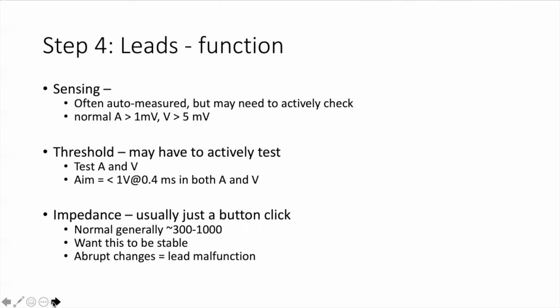Pacing threshold. Sometimes devices have an auto threshold check, though it's ideal to check the threshold yourself if the clinical question is whether the device has a lead malfunction. If they're looking to see why the patient was shocked for VT, it may be less necessary. To actively test, you're going to have to go to the tests tab on the device, and essentially you increase the rate on the channel you want to test, increase it above the patient's current rate, and walk down the output until you lose capture.